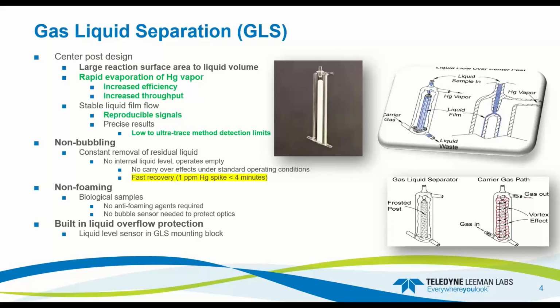Since it's a center post design, that means we don't have a reservoir of liquid, so it's not bubbling. So it's constant removal of liquid through the drain and waste lines, and that gives us a fast recovery of a mercury spike. Let's say we spiked it with 4 ppm or 1 ppm. Within 4 minutes, the sample is basically back down to baseline or a non-detect. Also, it's non-foaming. So if you're running biological samples, you don't have to add anti-foaming reagents. And it has a built-in overflow that will detect any issues with liquid flow. For example, if you happen to hook the peristaltic pump tubing for the waste line up backwards rather than draining, it would fill. The system would shut down.